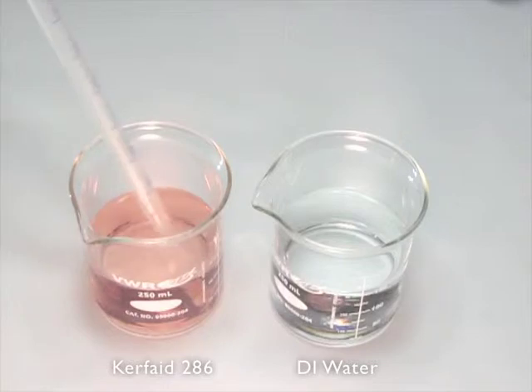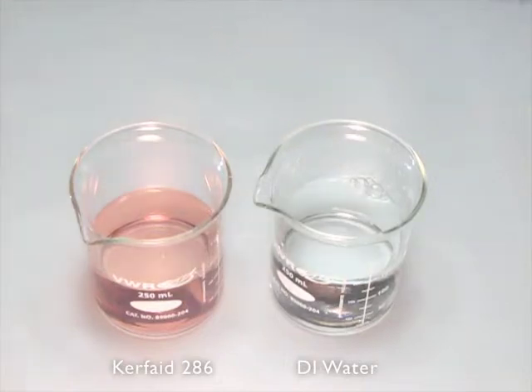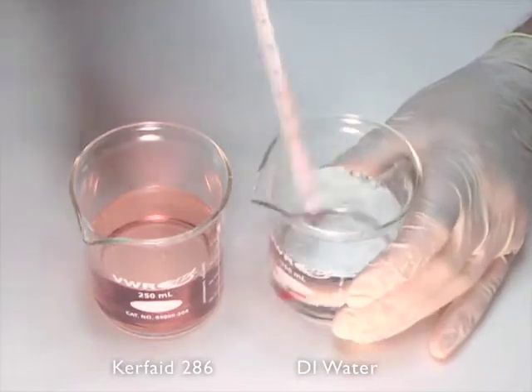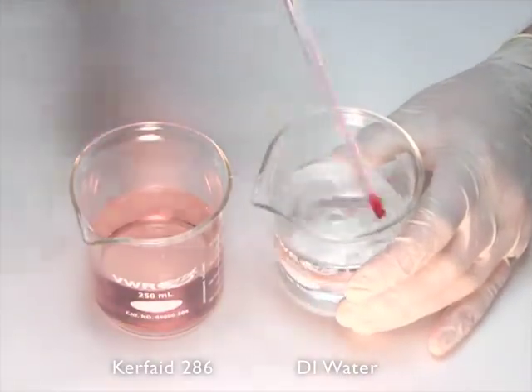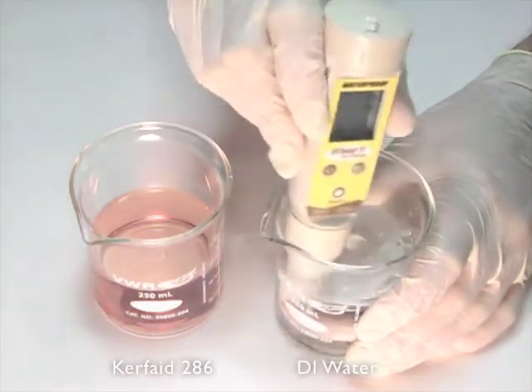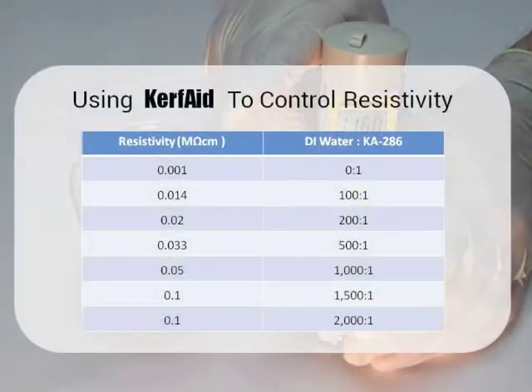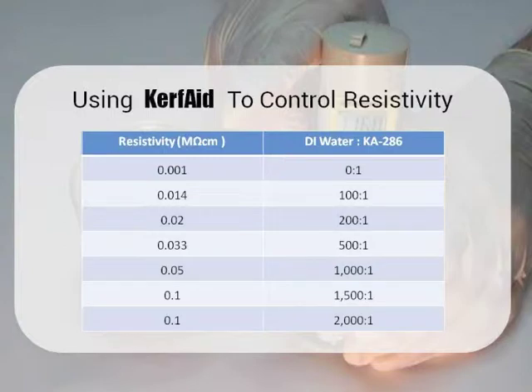To allow greater control of the resistivity, we at Dynatex have performed a simple experiment in which we varied the dilution ratio of KerfAid to deionized water and then tested the resulting solution for resistivity. Here is a table that lists the results. You can use these results to determine what ratio to use, or perform a similar experiment to find your own ideal ratio. It's simply a matter of using a specific amount of KerfAid 286 to set the resistivity of the dicing water.